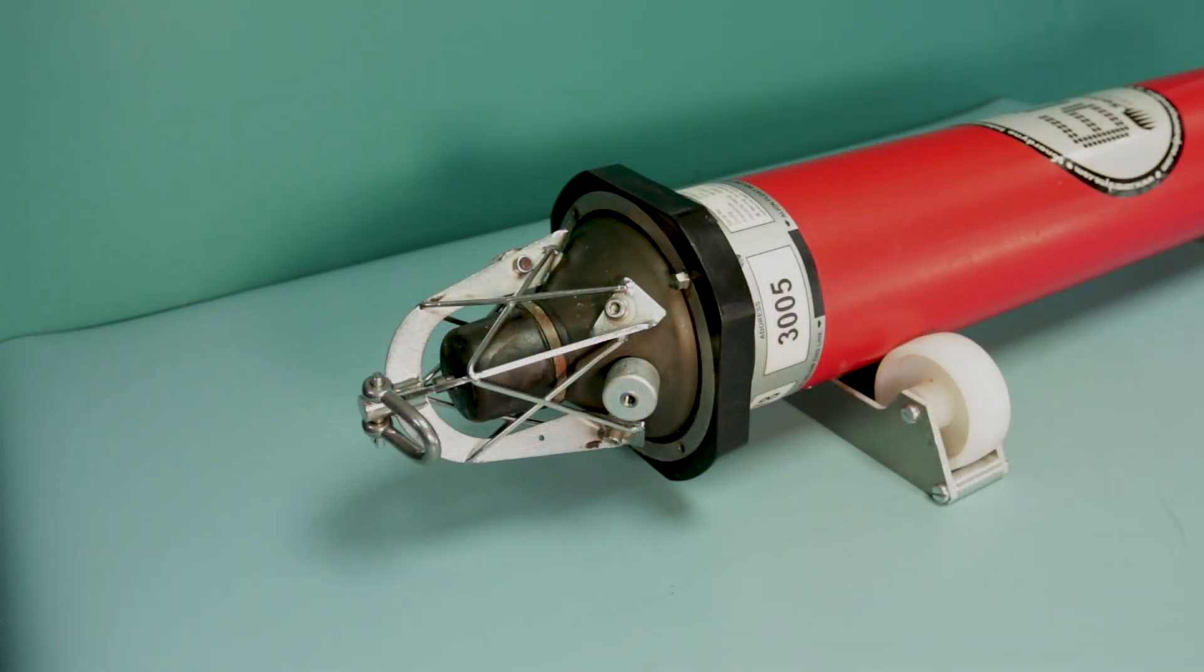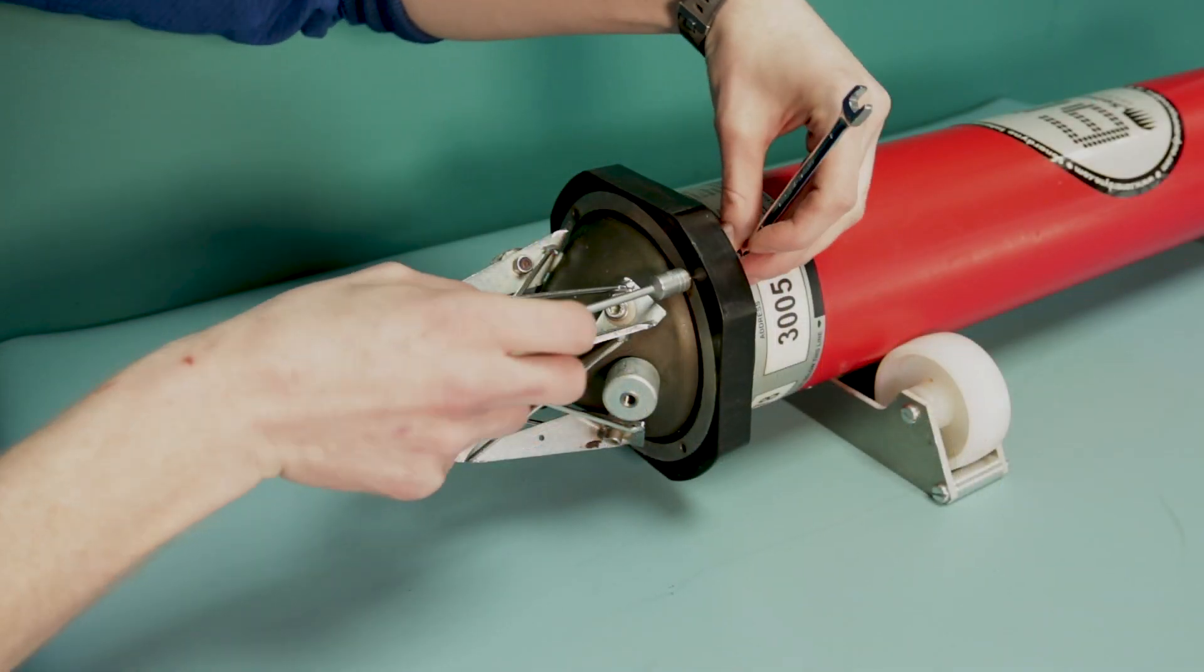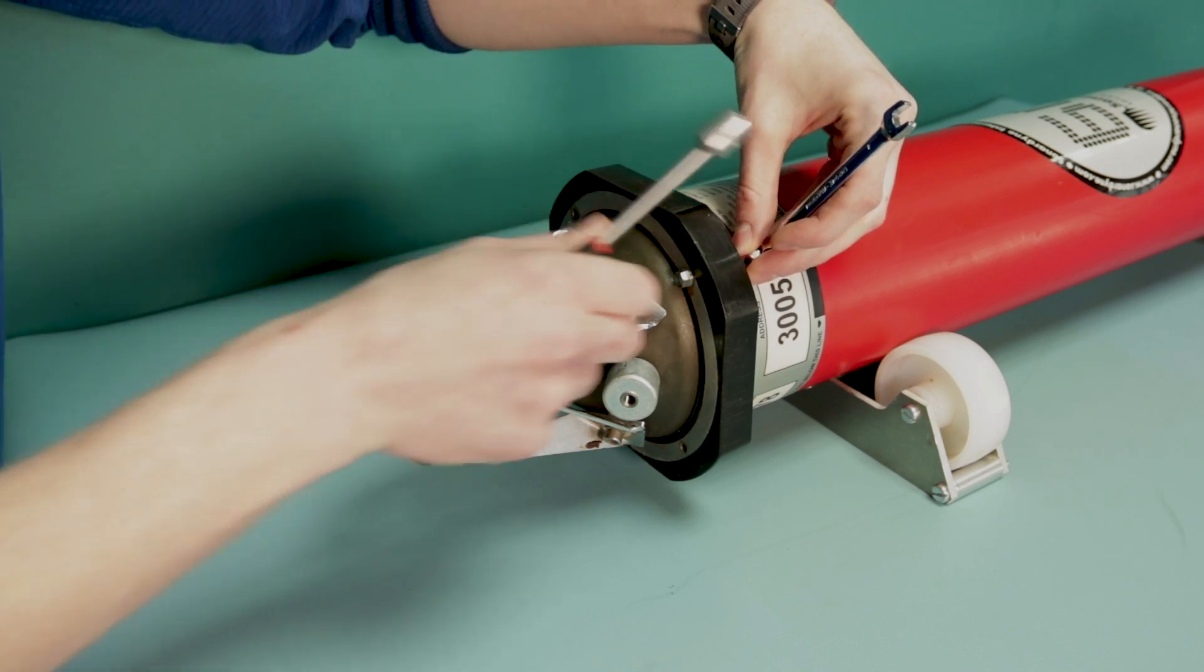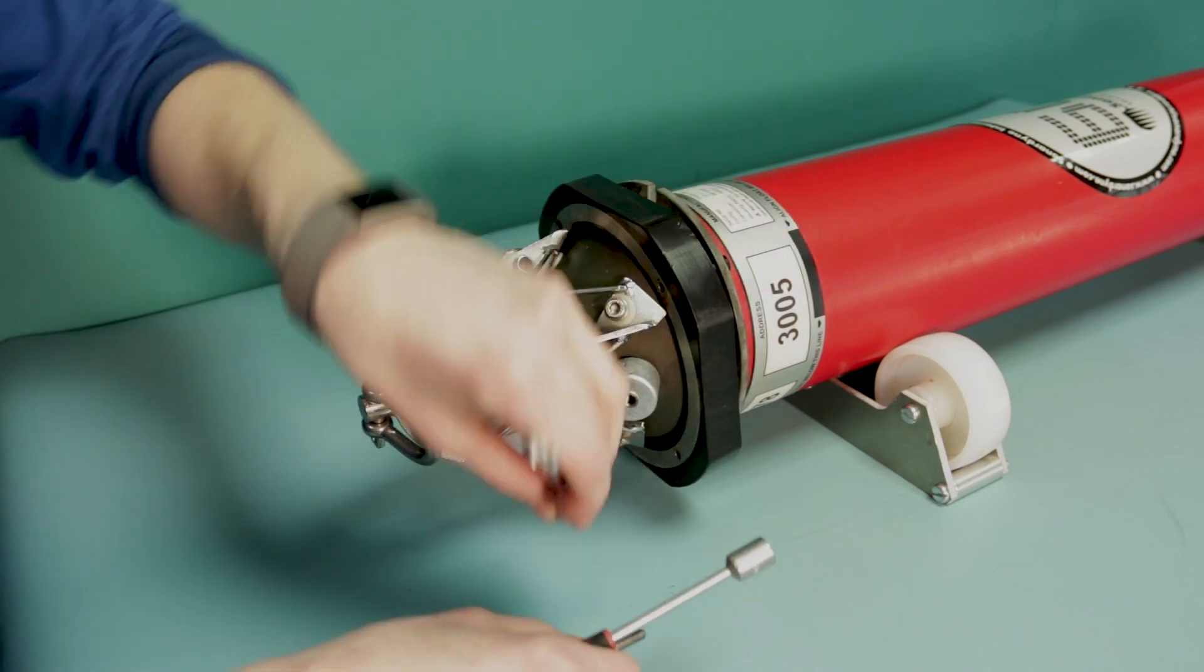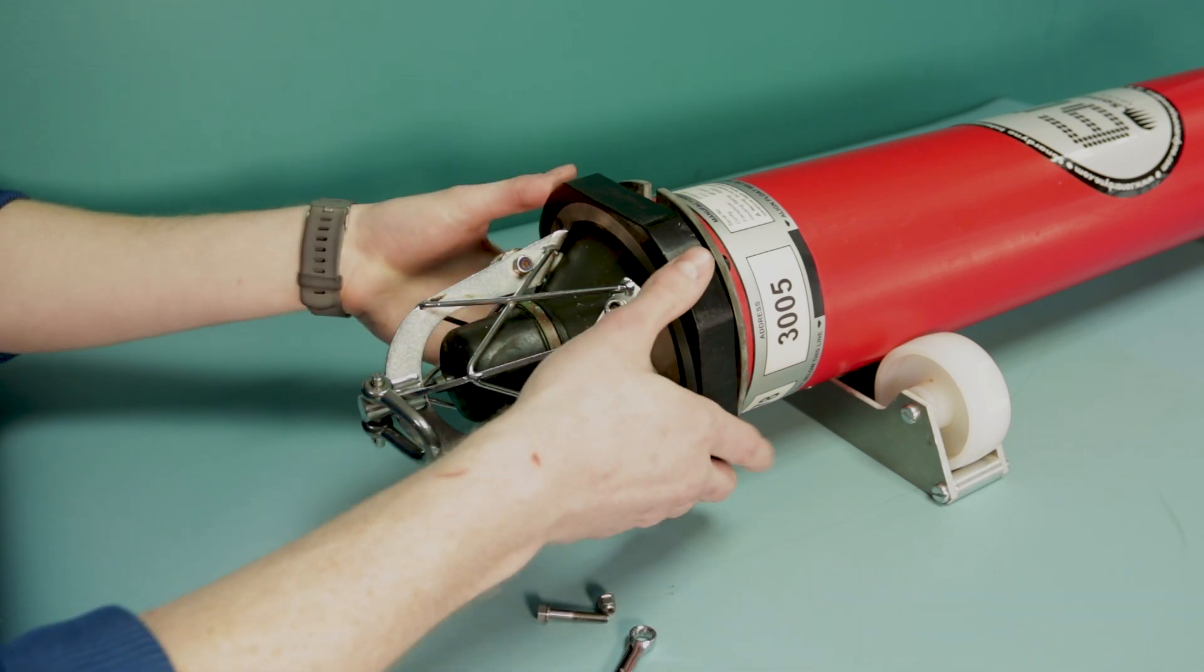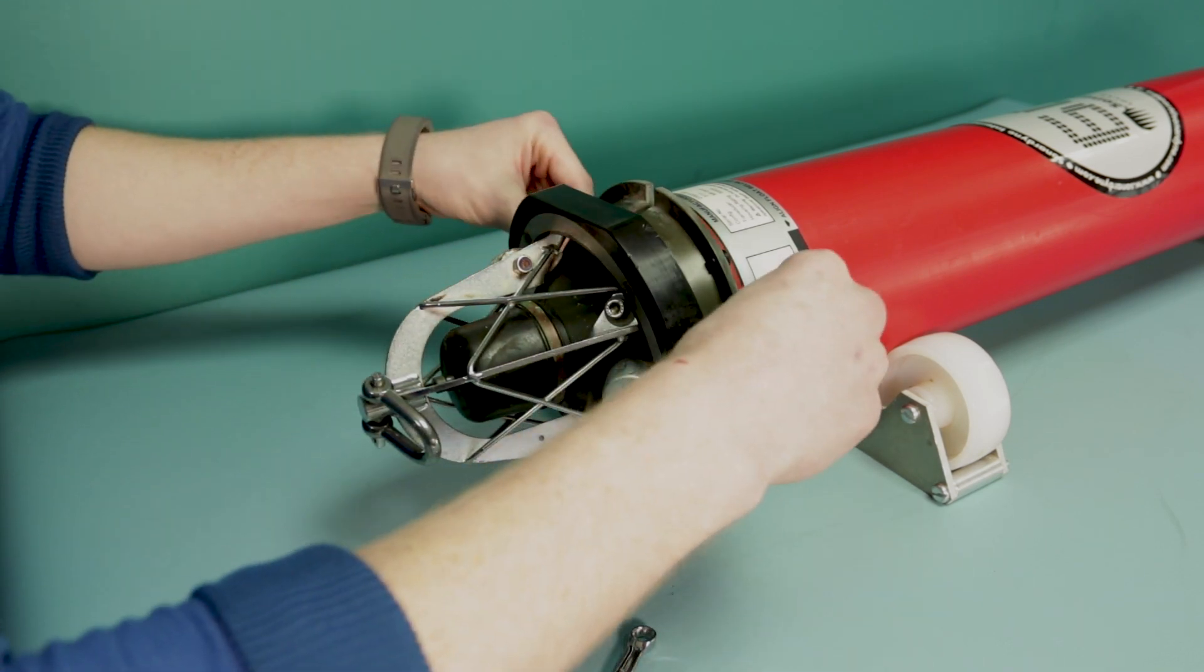On the transducer end cap, undo and remove the bolts and washers that hold the clamp ring in place. Push free the rubber bumper and remove the clamp rings from the housing.